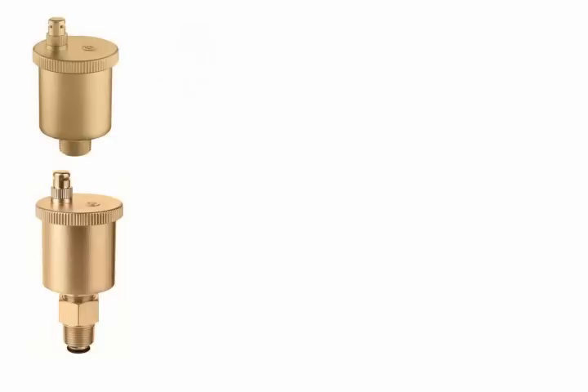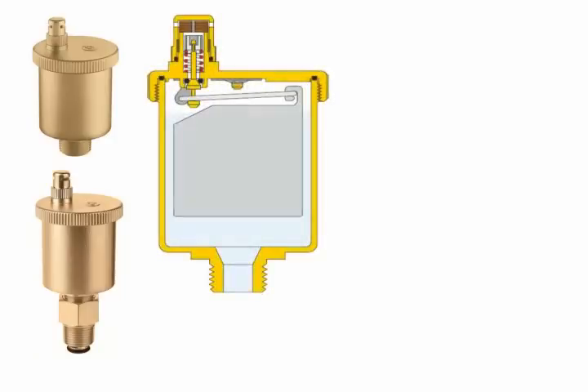Whether it's a Caleffi air vent or an Amtrol air vent or an Xylem or B&G, pick your brand. They operate very similarly. If you cut away that air vent, you have a float, and the blue indicates the water level, and the white indicates the air column. In this state, nothing's going on.